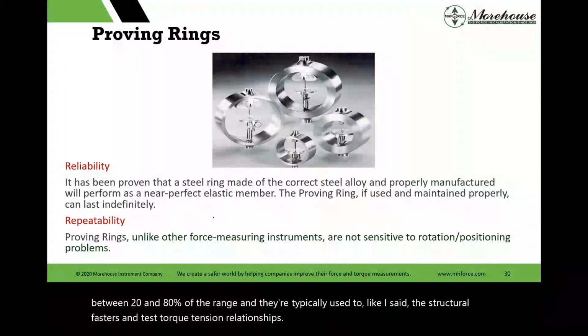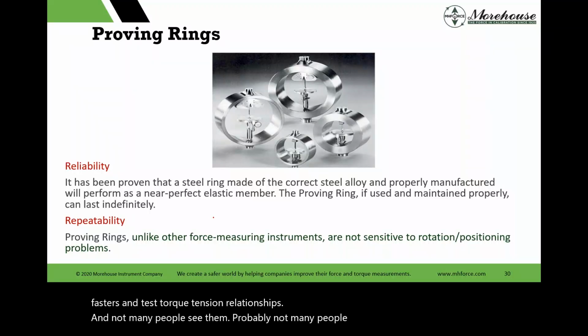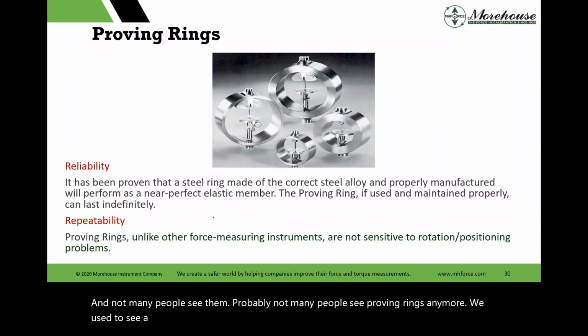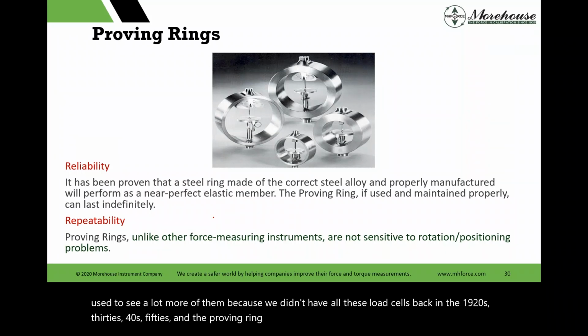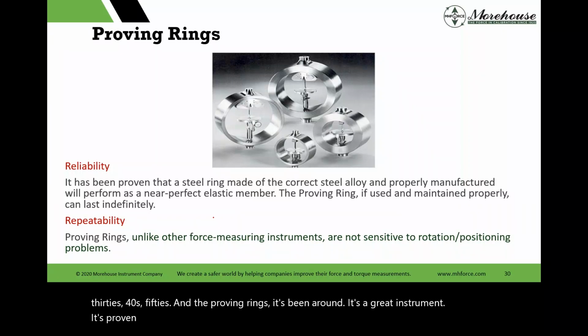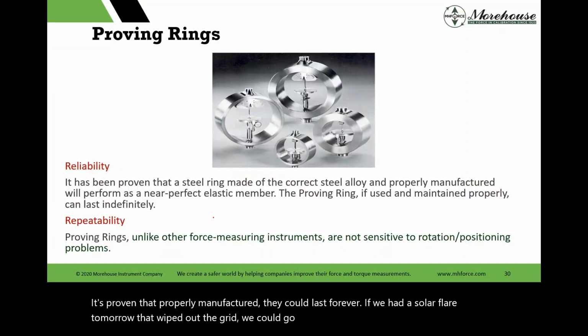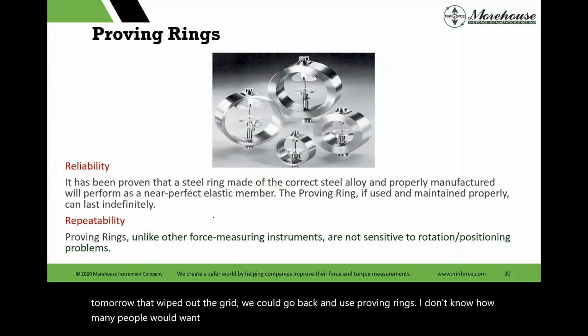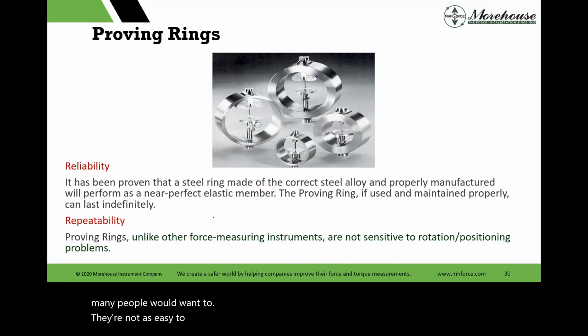And not many people see them. Probably not many people see proving rings anymore. We used to see a lot more of them because we didn't have all these load cells back in the 1920s, 30s, 40s, 50s. The proving ring has been around. It's a great instrument. It's proven that, properly manufactured, they could last forever. If we had a solar flare tomorrow that wiped out the grid, we could go back and use proving rings. I don't know how many people would want to. They're not as easy to use as load cells for sure, but they last, and they are a really good check standard for your system.